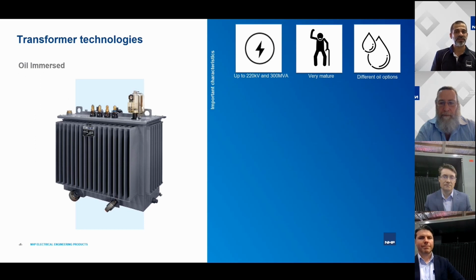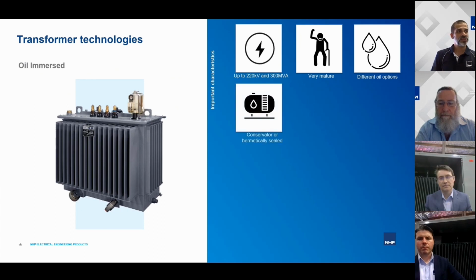One of the common ones these days is the standard mineral oil transformer. And then you could have a high flash point oil transformer. There are a couple of different options with high flash point oils, which can be either a synthetic version or a soy ester based version as well, which is more environmentally friendly. Dimitri, you had some good points to talk about around a couple of other things around oil transformers.